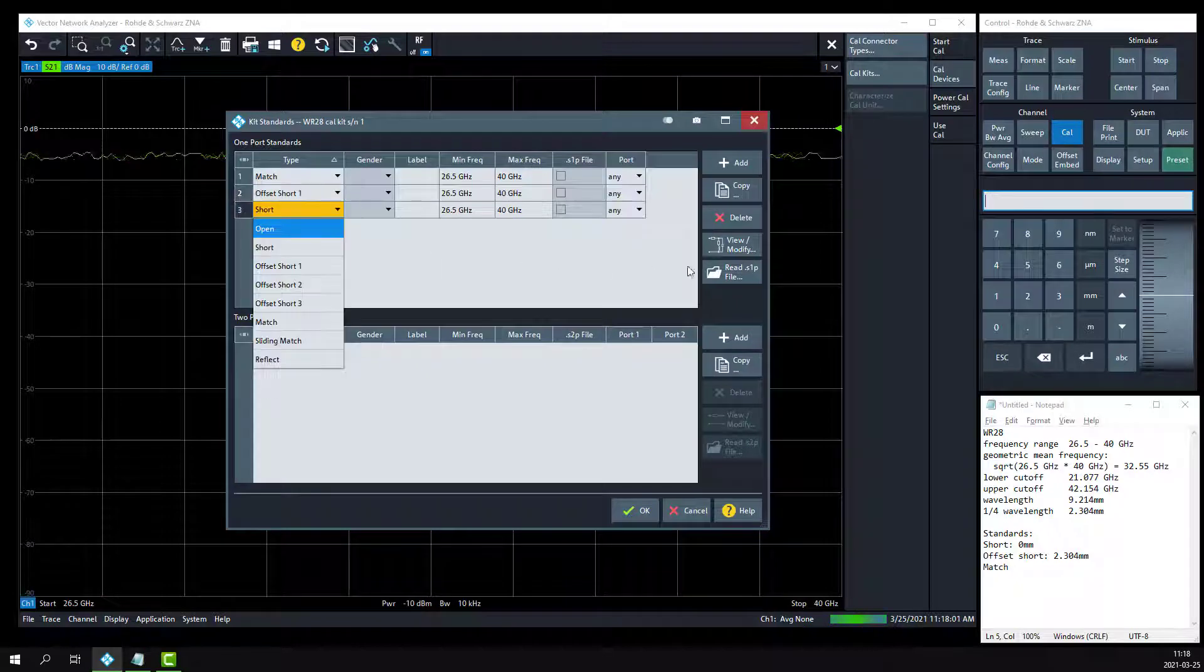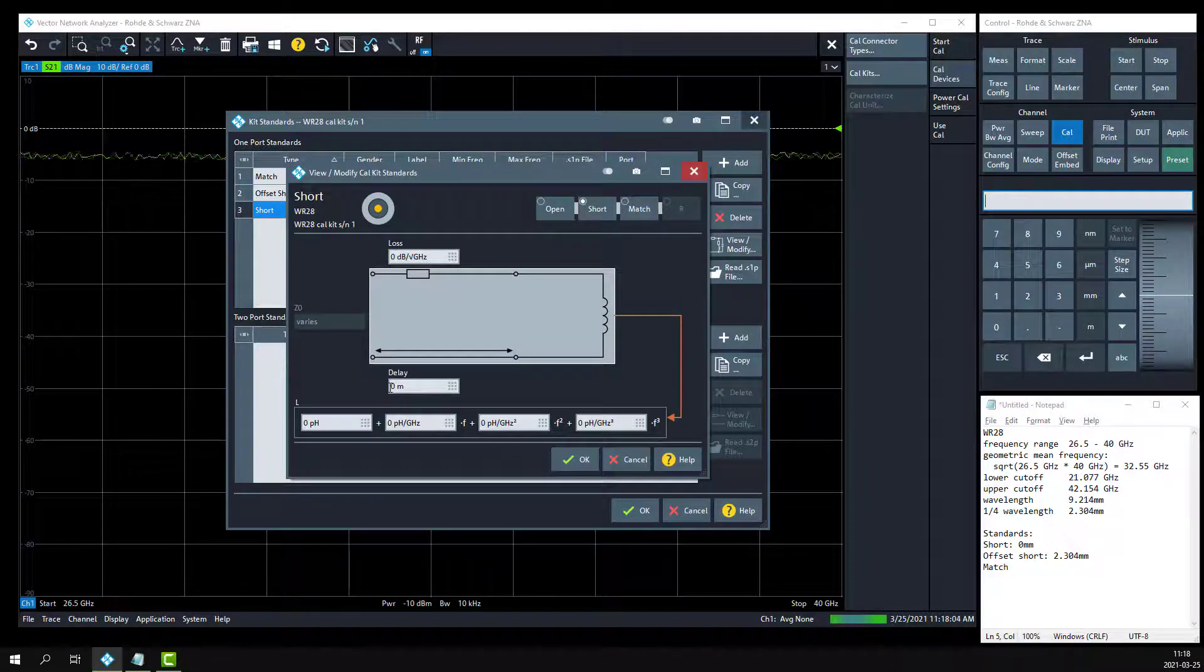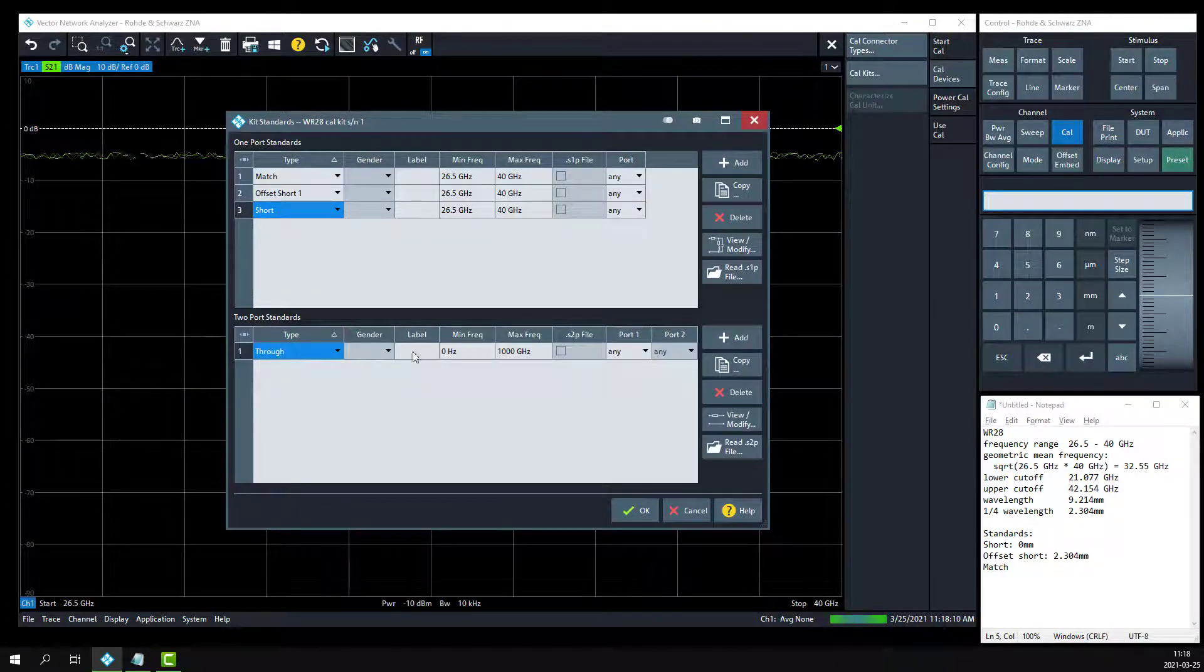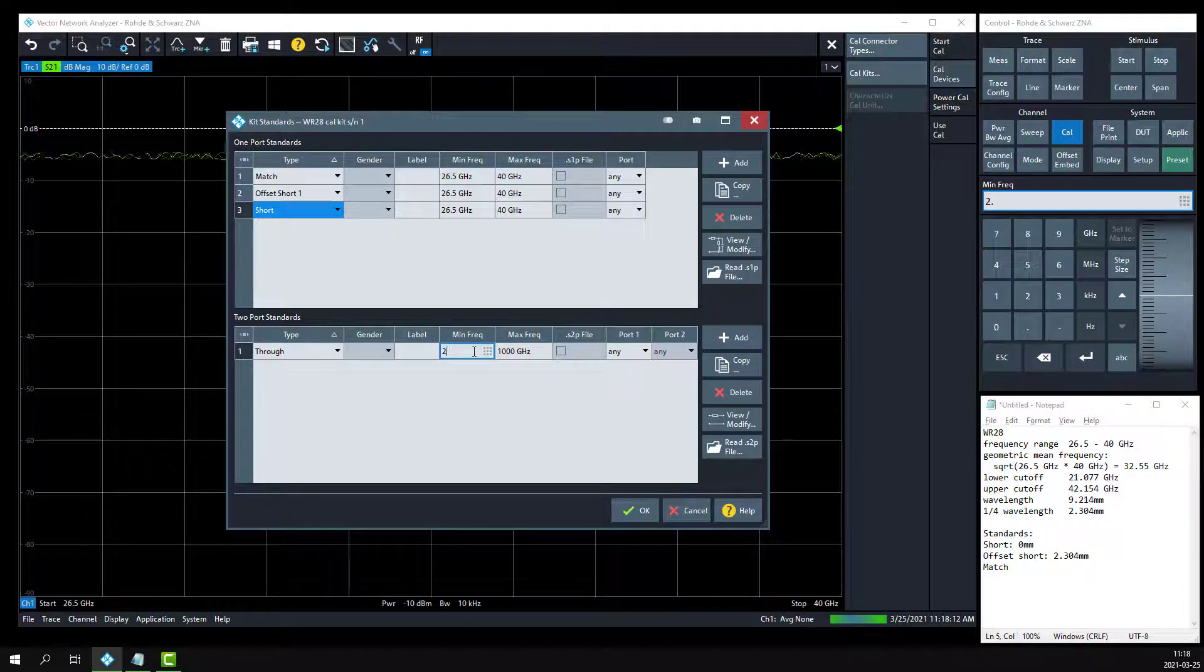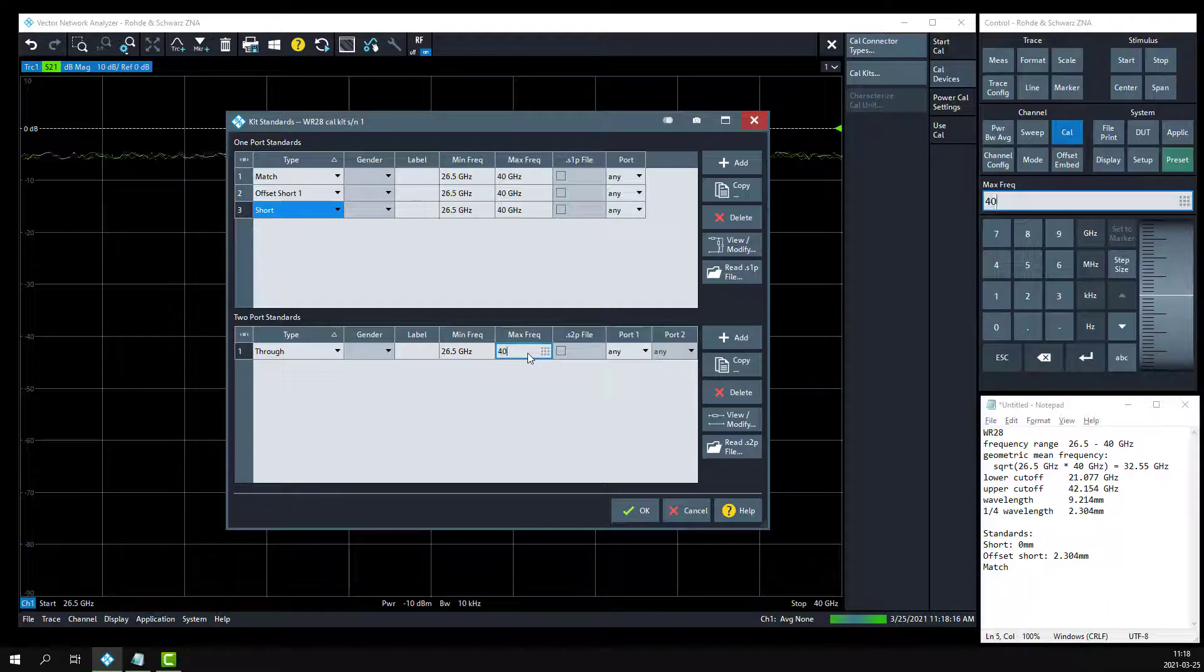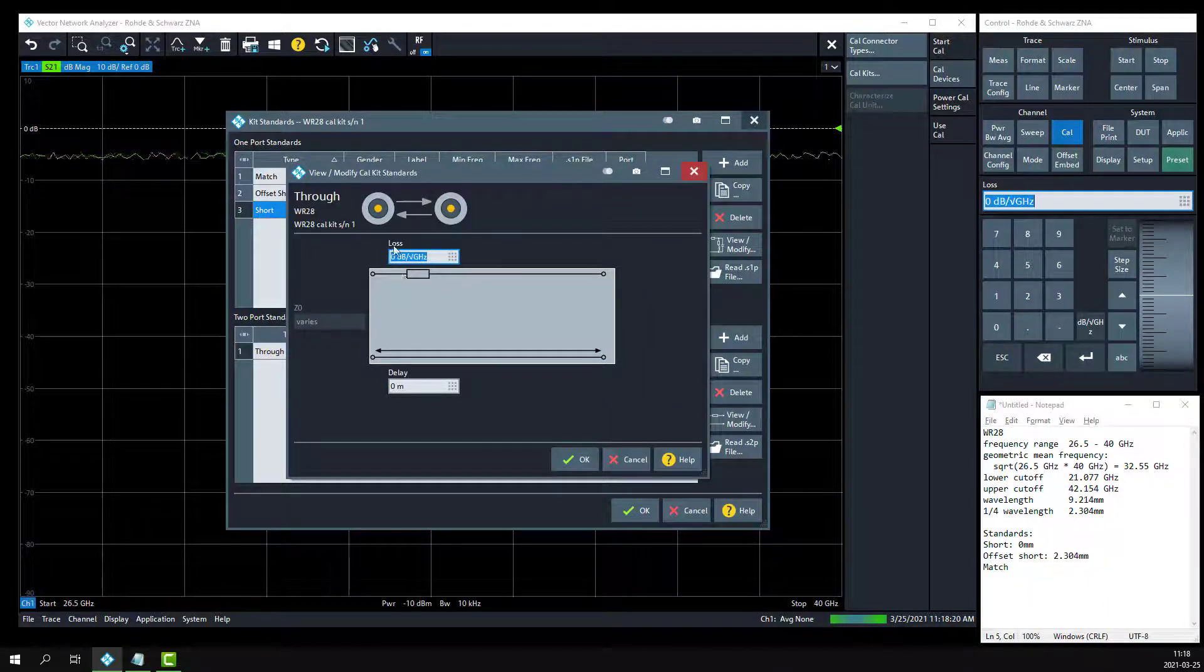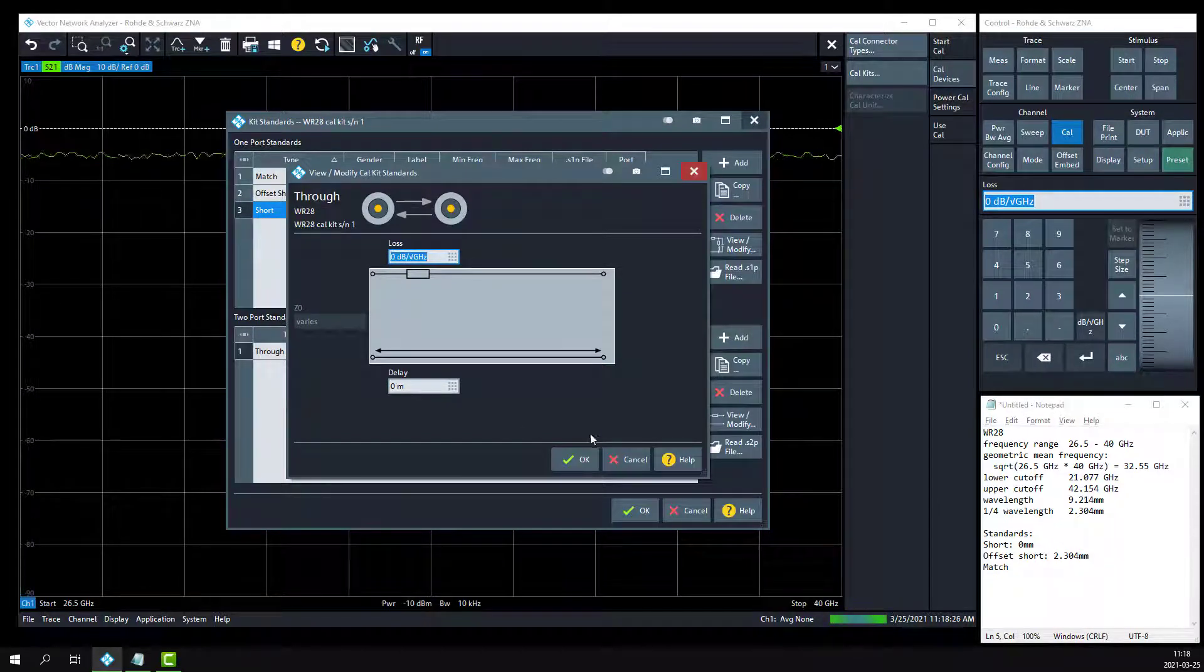Click on the short button, and we'll verify this is a zero millimeter length short. And then we'll add a two port standard. We're going to do a zero length through. So for this through, the 26.5 gig min frequency and a 40 gig max frequency, we'll verify that it has zero length and zero loss. In this case here, we're just going to connect the waveguide on port 1 and the waveguide on port 2 together.